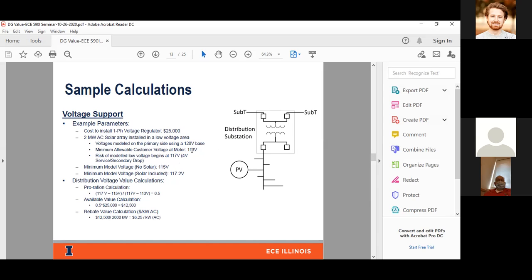In the planning criteria, just like we have normal and emergency operation limits for the distribution transformer, here we have a minimum allowable voltage at the meters of 113, and the risk of low voltage begins at 117. The minimum is 113 per law, and 117 is where we see risk. Anything above 117, we don't initiate any projects. Anything at or below 117, we start initiating projects. So we run the model for this circuit. Without solar, we found the voltage in that specific area to be 115 volts. If you add that 2 megawatt solar at that location of the voltage violation, you've improved to 117.2, so you've already eliminated that voltage violation. Then we go back to the same concept of prorating the value.